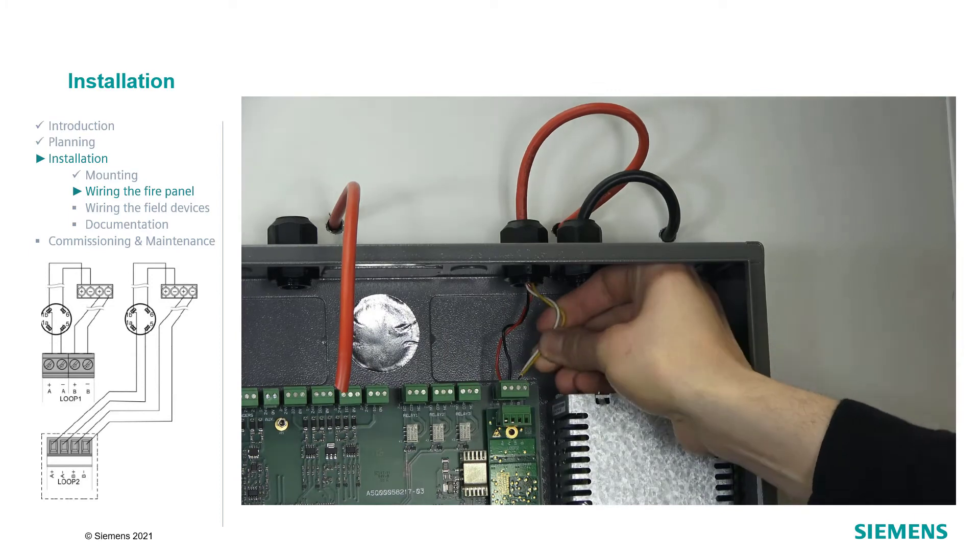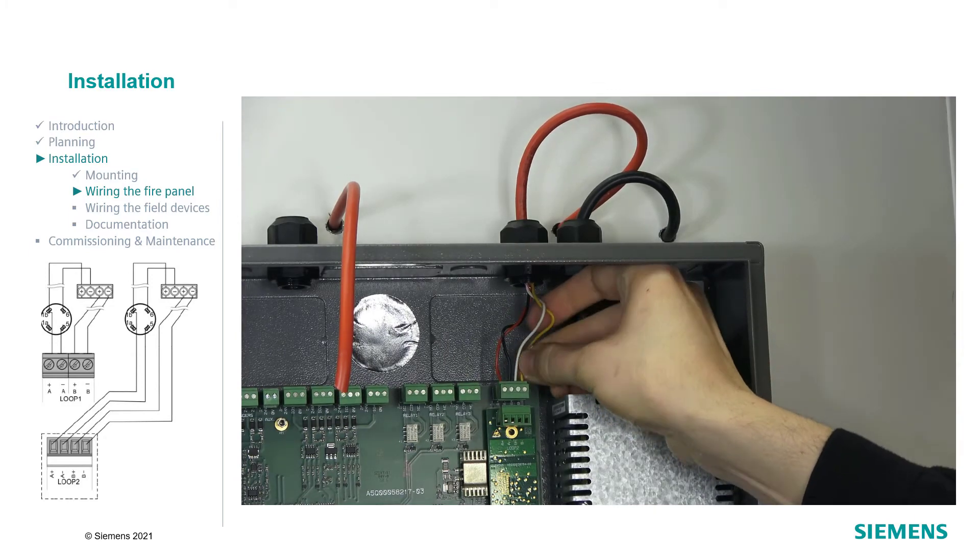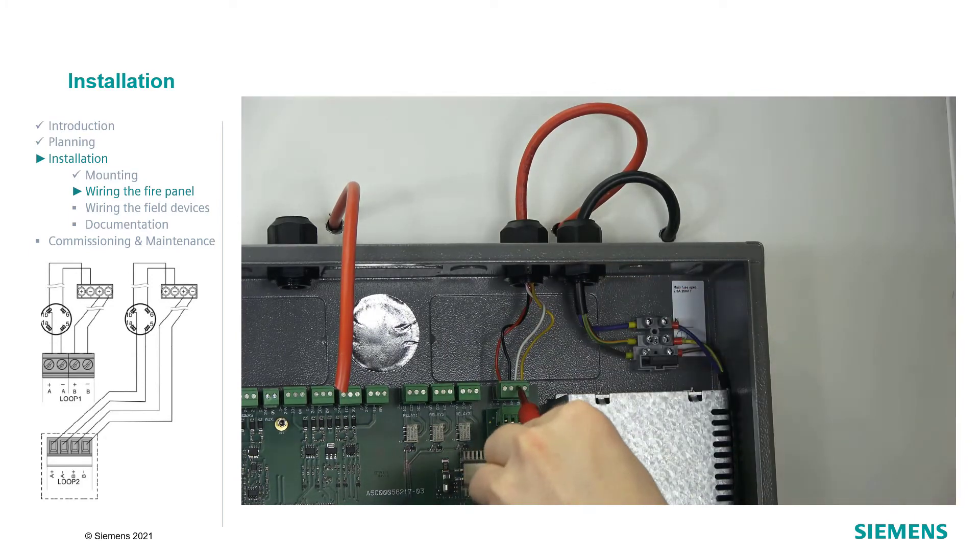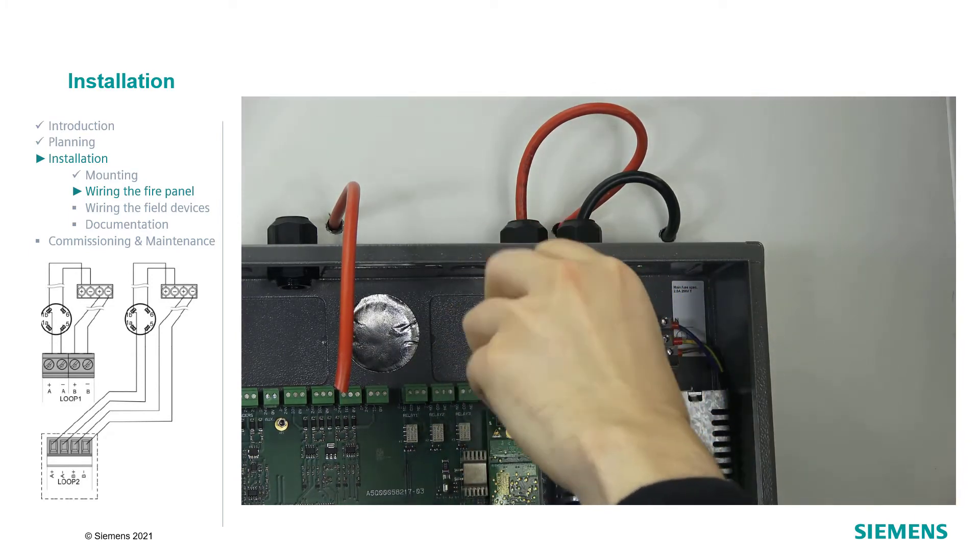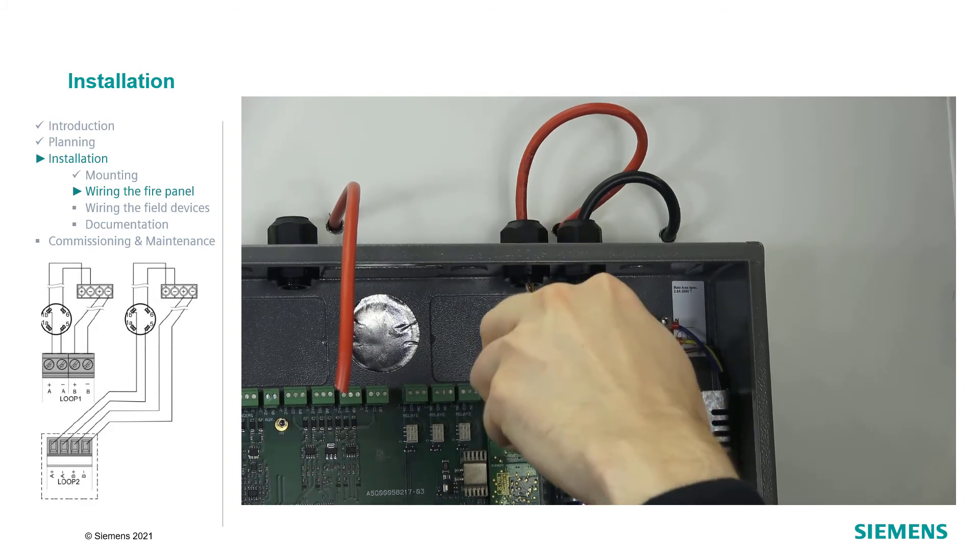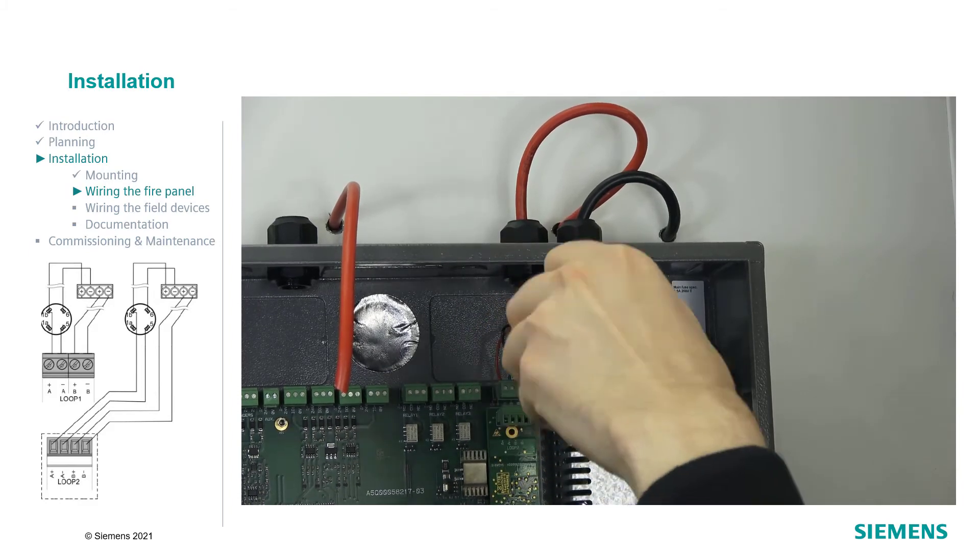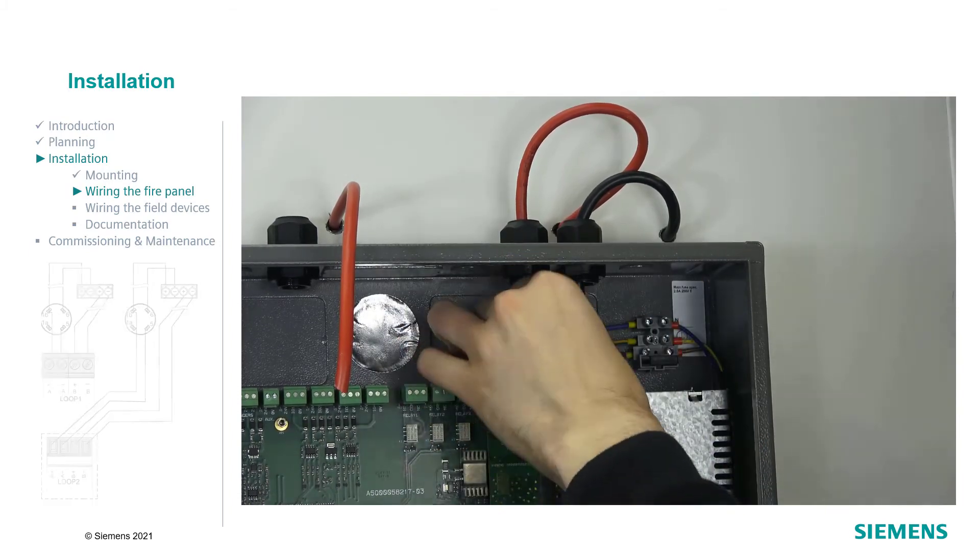For the FC-362, follow the same steps for the connection of the second loop. Please keep in mind that a maximum of 126 devices can be connected to the detector line.